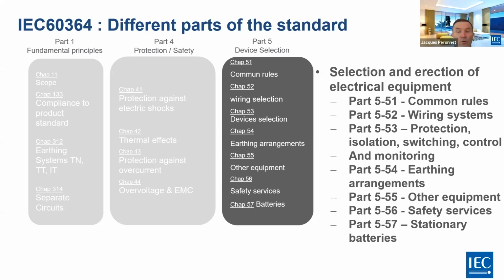So this part is key when you are going to use the protection against electric shock by automatic disconnection of supply. So it will describe how to make the earthing electrode and all the earthing arrangement to make sure that in case of any fault, you are going to carry the current through this earthing arrangement. In the part 55, we are going to describe how to install other equipment. So it could be lighting, it could be multi-source equipment, multi-supply, and auxiliary services.